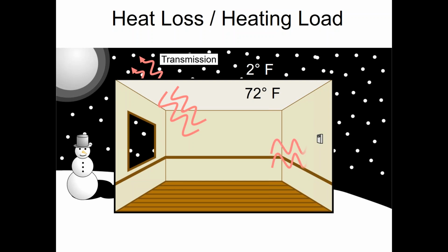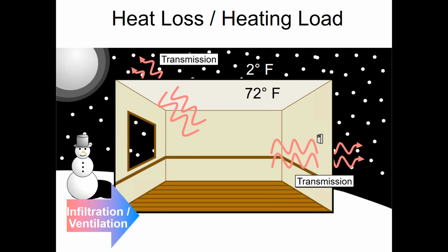The information you need to put into the load calc: geography is important, which is why EDS uses the address. That way they can pull in the geographical weather data, and they can use that as a starting point so you don't have to go look it up in a table, or so you don't have to go guess at it, which is even worse. In this case, for this slide right here, I'm using 72 as my indoor heating temp and 2 degrees as my outdoor temp. I'll show you why I use those particular numbers on this particular slide. I'll show you that in a minute. But right now, those are the numbers I'm using.